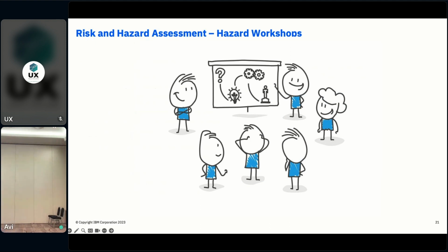What I am doing as a clinical safety officer is facilitating what we call a hazard workshop. It's a multidisciplinary meeting involving designers, developers, technical architects, clinical folk like myself, and users, and we try to break the solution. We evaluate, we try to identify hazards, brainstorm as many as we can, and then evaluate the risk of those hazards and document them. Okay, we've identified a hazard, and evaluated the risk. How can we make a design change to reduce the risk? How can we make a process change? Can we put in place better training? And all these other things to think about, again, reducing that risk.